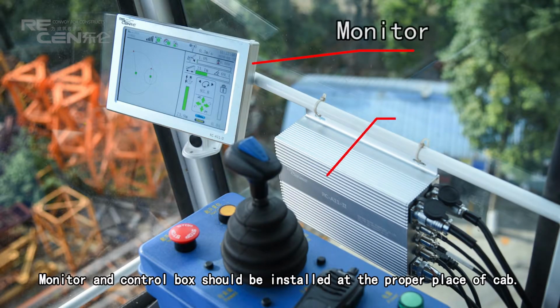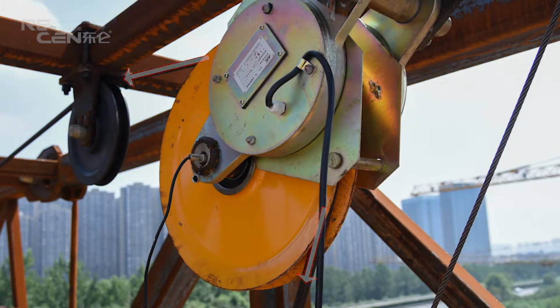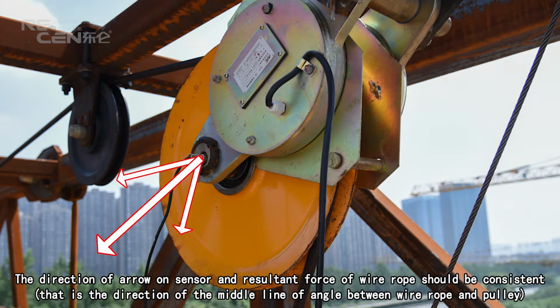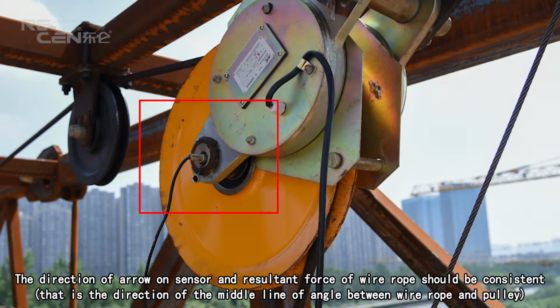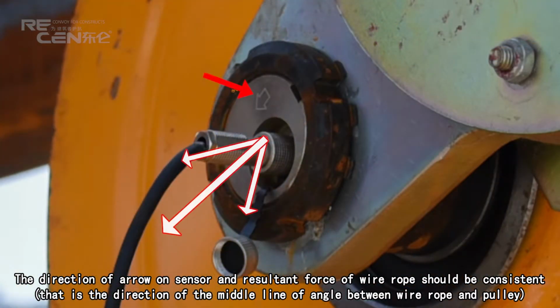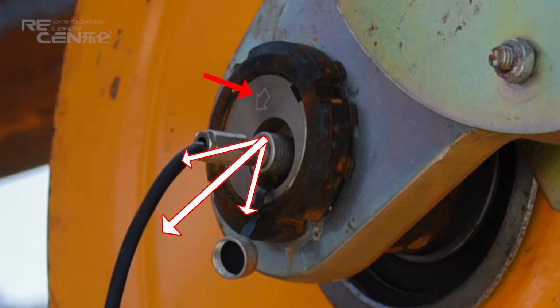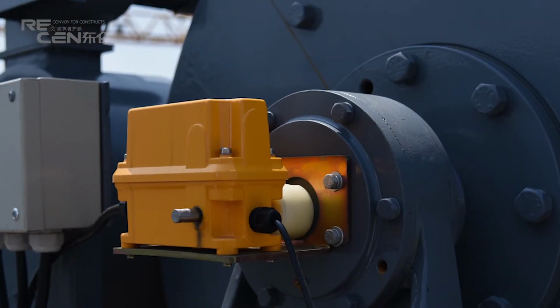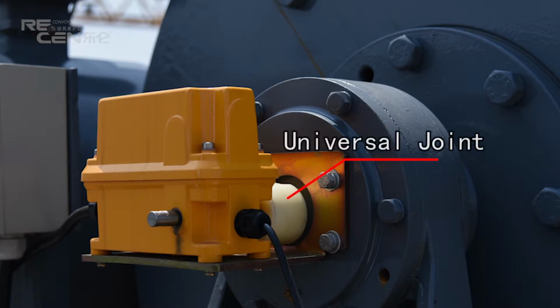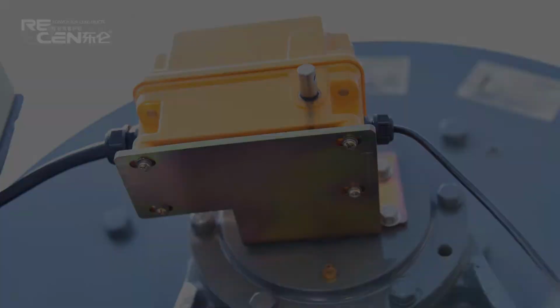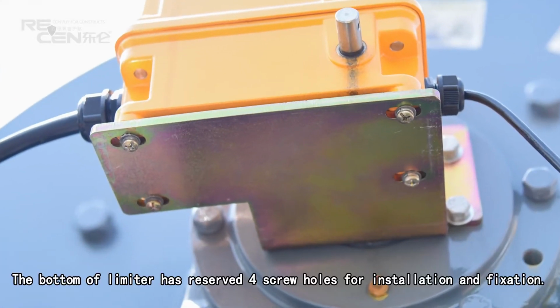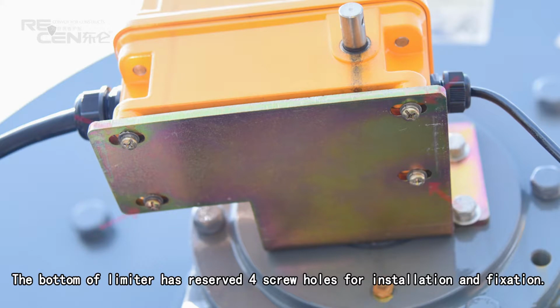The monitor and control box should be installed at a proper place in the cabin. The direction of the arrow on the sensor and the resultant force of the wire rope should be consistent, that is, the direction of the middle line of the angle between the wire rope and the pulley. The bottom of the limiter has reserved screw holes for installation and fixation.